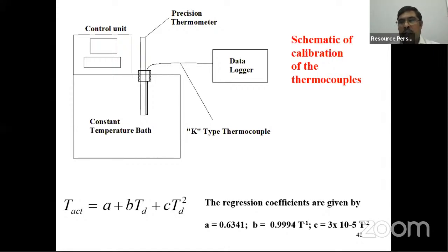At least the error should be within plus or minus 0.1 degree Celsius. The bath should also have very good temperature stability - wherever you measure the temperature, it should give a uniform value. So first you set the temperature at 0 degree, and see the thermocouple response, whether it shows 0 or not. Then for every 10 degree, you have to increase.